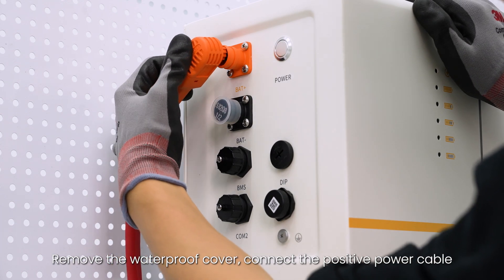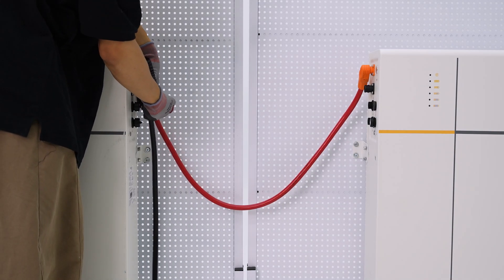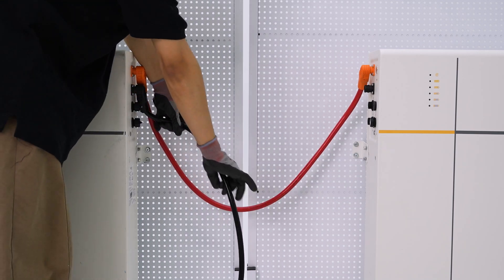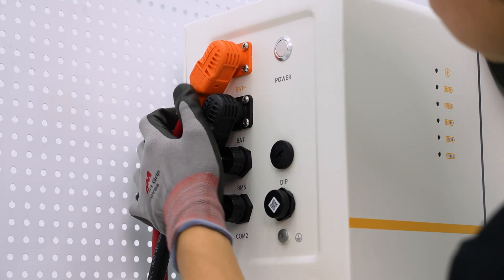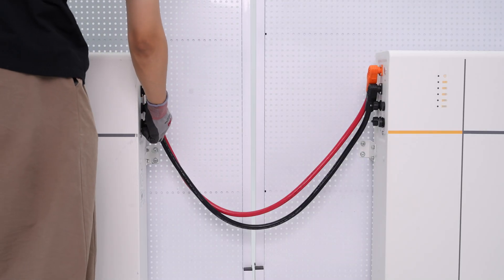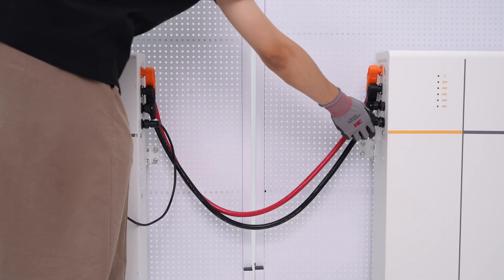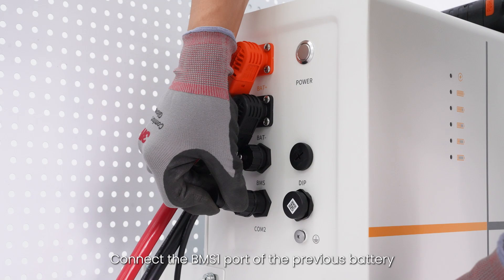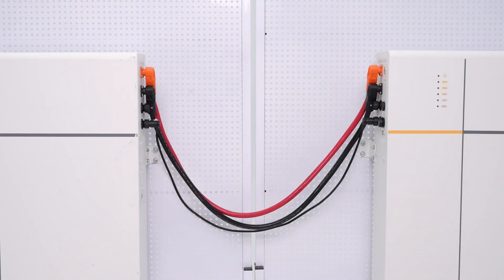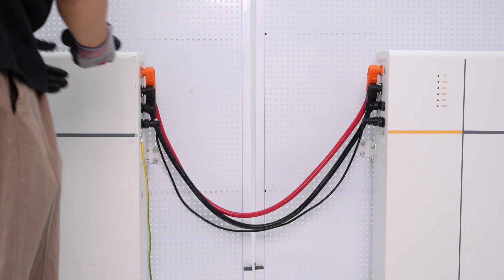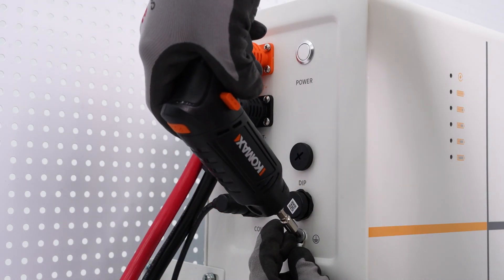Remove the waterproof cover and connect the positive power cable. Remove the waterproof cover and connect the negative power cable. Connect the BMS1 port of the previous battery to BMS2 port of the next battery. Connect the PE cable.